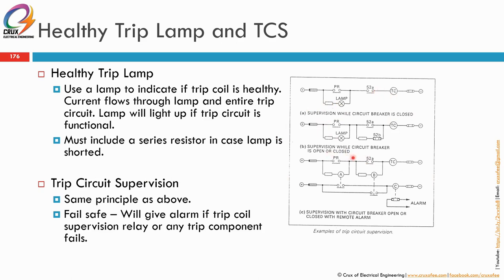So supervision while the circuit breaker is open or closed. So these are the conditions. We have a lamp going through the circuit breaker. When the breaker is closed, it will flow through here. This contact 52A will close. When the breaker is in the open position, it will go through this contact here. So there are two resistors. So this part B here is monitoring the trip circuit supervision in both open and closed condition.